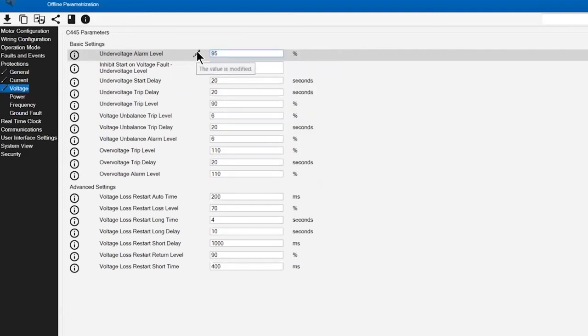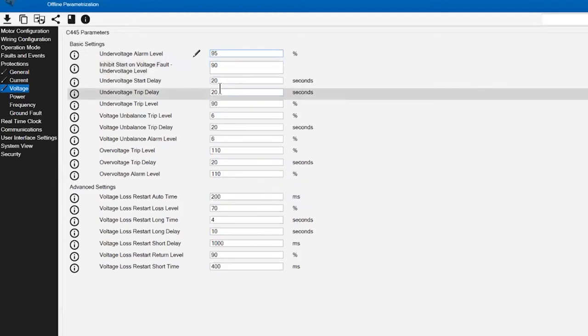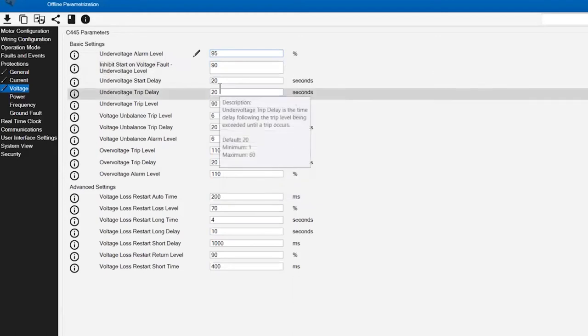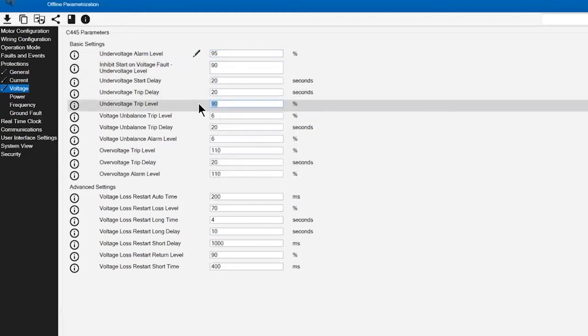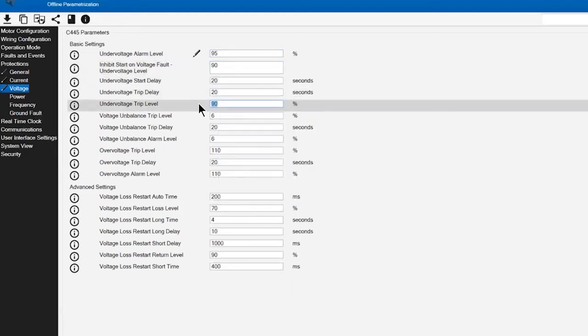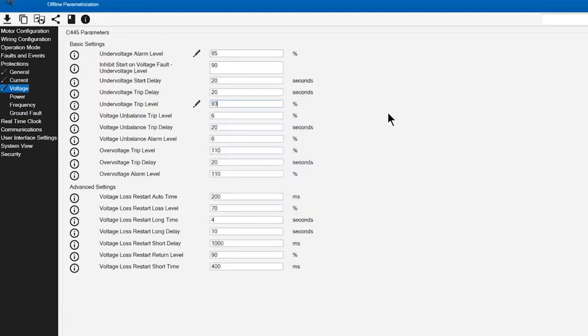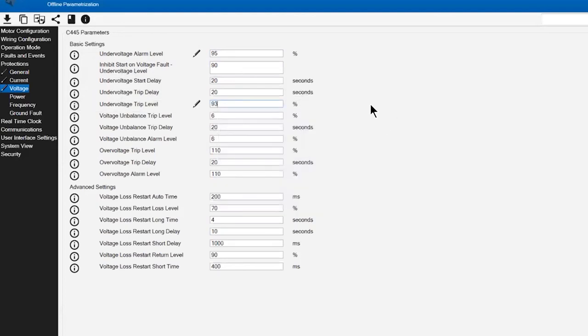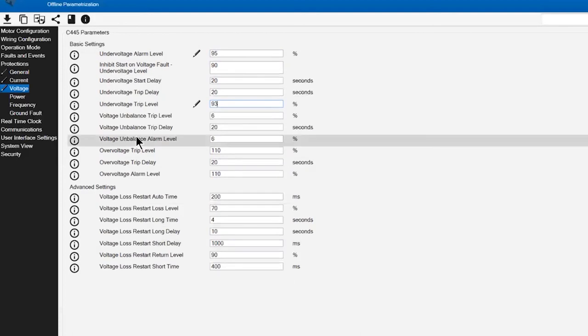This is that pre-warning that something is occurring. I'm going to set that at 95% to give me an early window, and then my under voltage trip level, aligning more with NEMA considerations, I'm going to set at 93%. So I'm going to get an early warning at 95%, and if the condition doesn't correct, I'm going to ultimately result in a trip of that motor circuit at 93%.